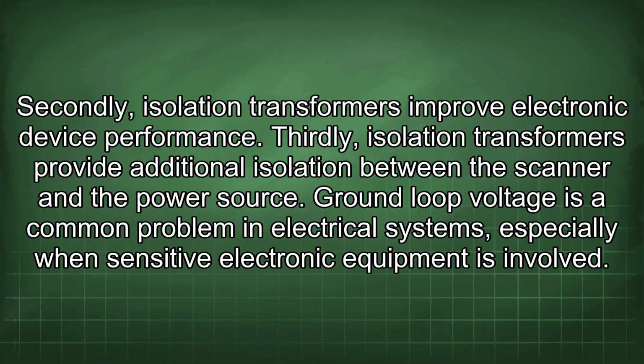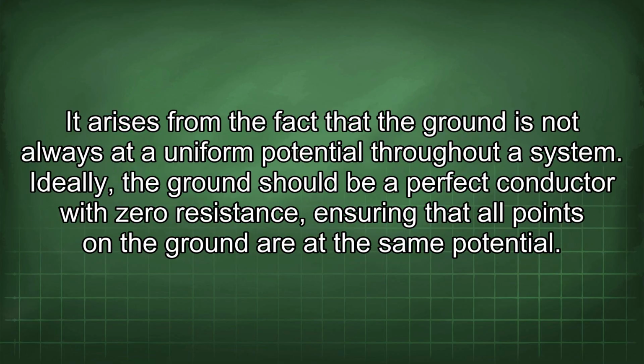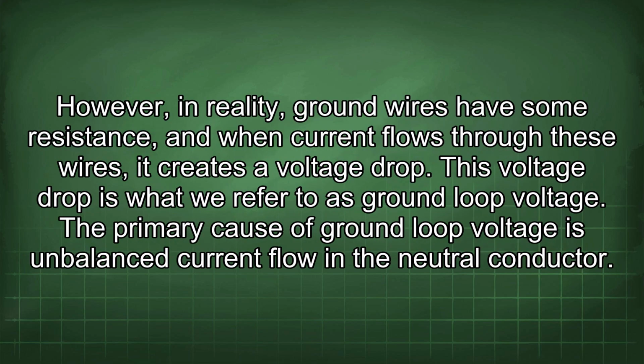Ground loop voltage is a common problem in electrical systems, especially when sensitive electronic equipment is involved. It arises from the fact that the ground is not always at a uniform potential throughout the system. Ideally, the ground should be a perfect conductor with zero resistance, ensuring that all points on the ground are at the same potential. However, in reality, ground wires have some resistance, and when current flows through these wires, it creates a voltage drop. This voltage drop is what we refer to as ground loop voltage.